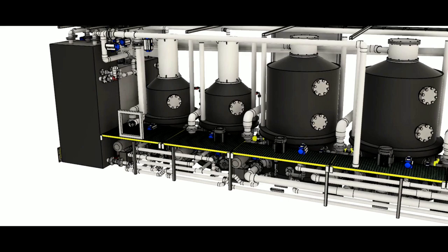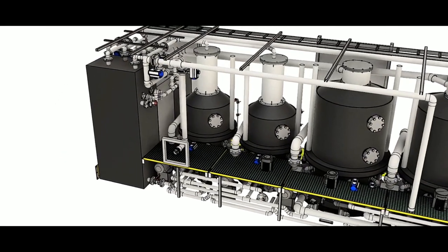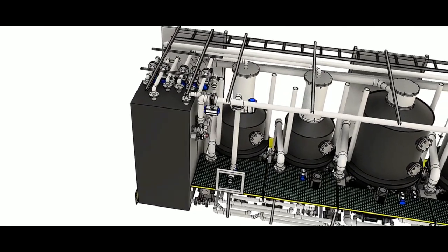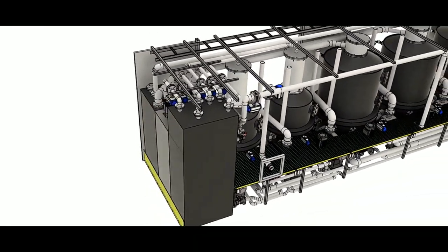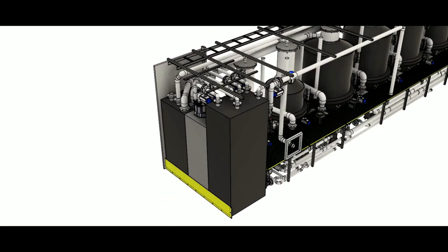And then from the tertiary fractionate, that runs into the third tank on the far side, and that builds up there. Bearing in mind that for every, say, 1 million litres, and this unit will process just under 1 million litres a day at the most rapid cycle, it'll produce about 600 mils of tertiary fractionate. So about a milk carton of really concentrated fractionate, which is actually getting back to the concentration levels that it was introduced into the environment as a firefighting foam in the first place. So we're really turning back time. Really closing the loop, aren't we?